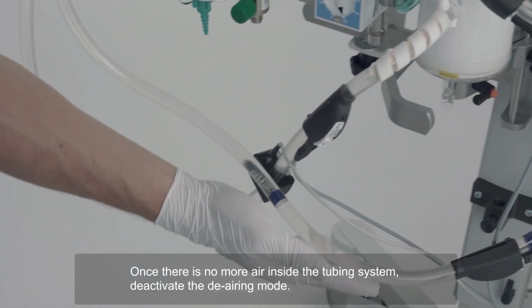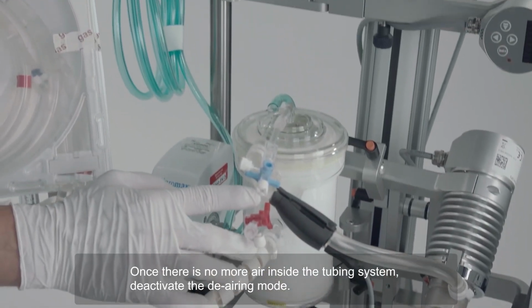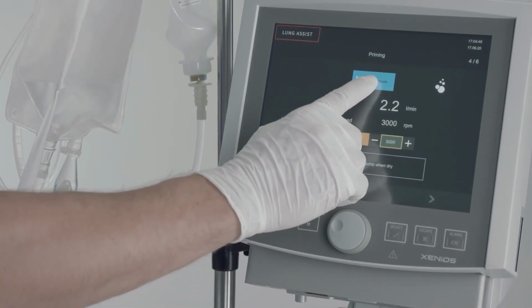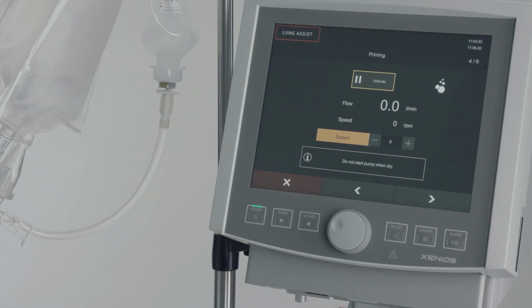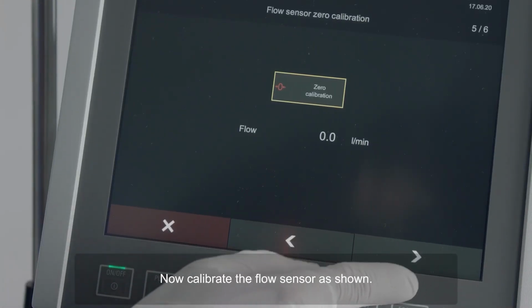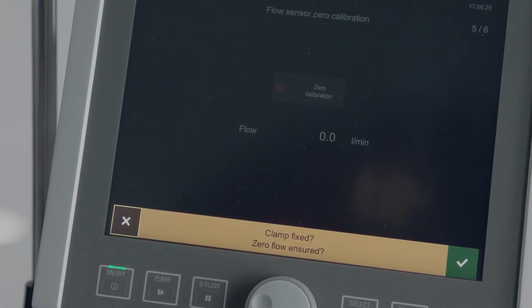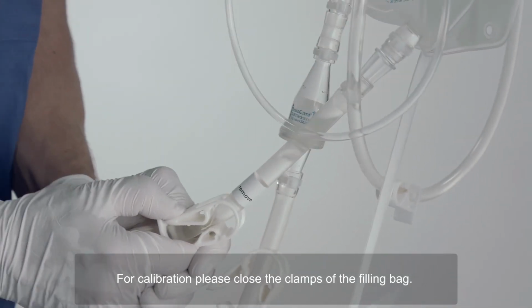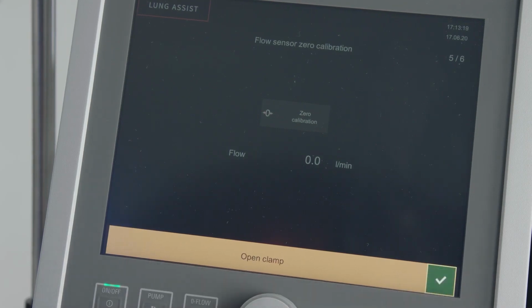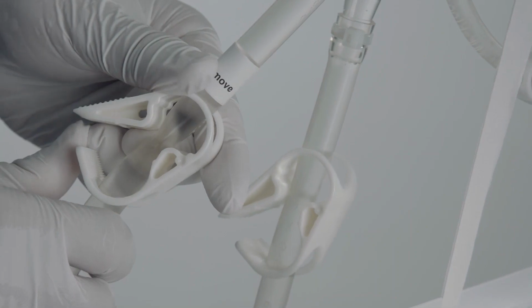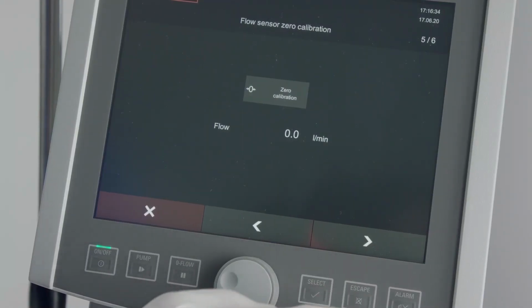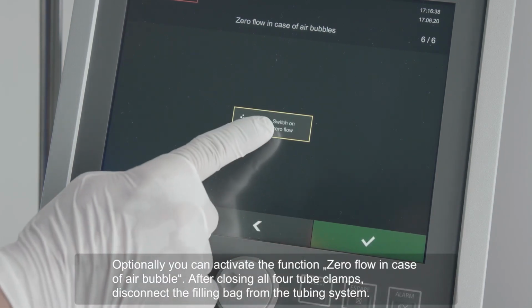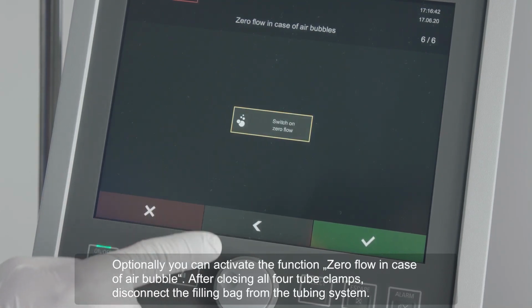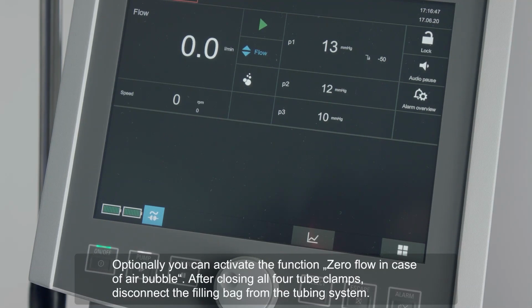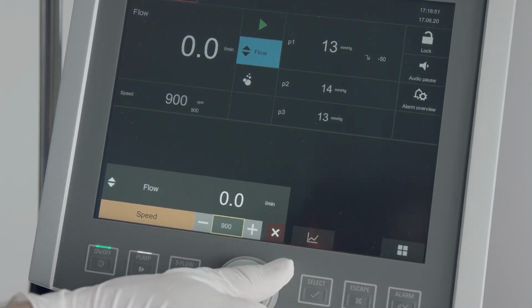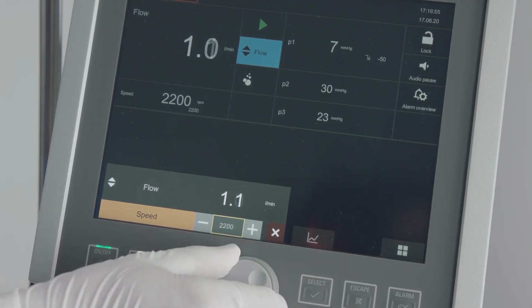Once there is no more air inside the tubing system, deactivate the de-airing mode. Now calibrate the flow sensor as shown. For calibration, please close the clamps of the filling bag. Optionally, you can activate the function Zero Flow in case of air bubbles after closing all 4 tube clamps. Disconnect the filling bag from the tubing system. The priming is completed.